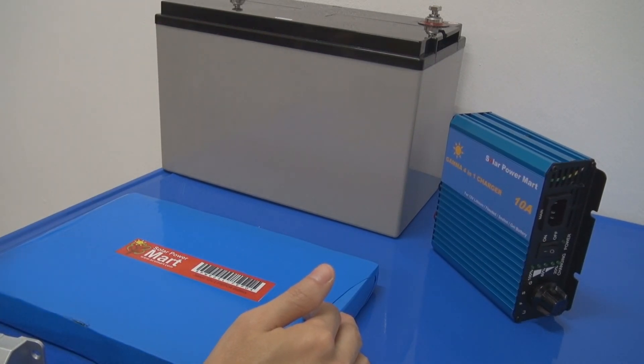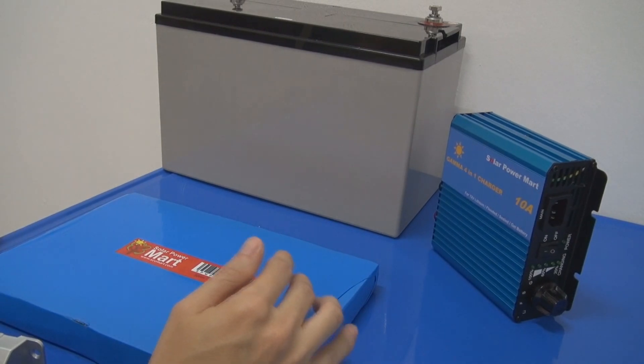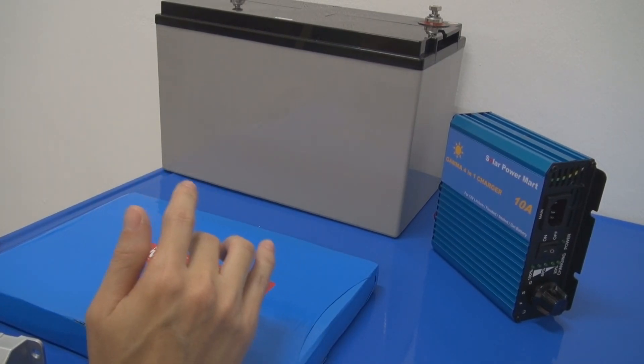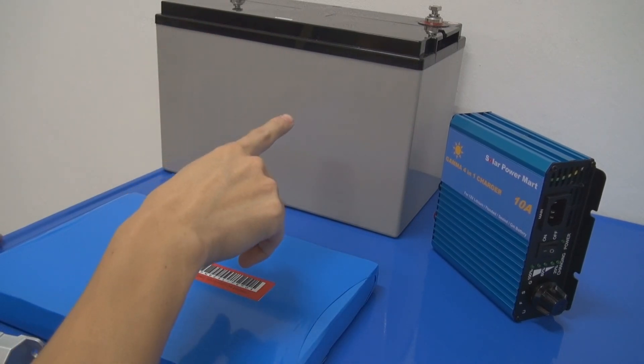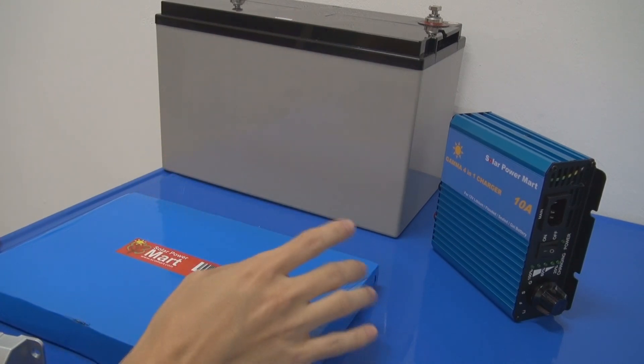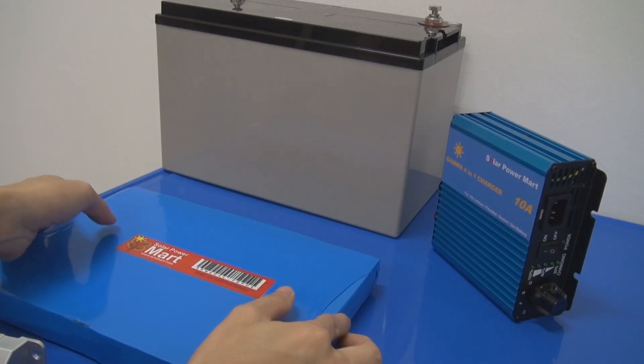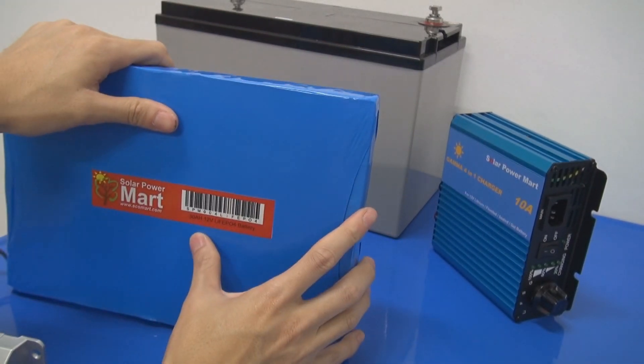Let's say you design your street light system. Every day you take about 20% DoD discharge because you want to prolong it and let it last about 2 years. Because you add in the temperature and things like that, if you cycle about 20% a day, it will last about 2 years plus with the temperature factored in. And let's say you upgrade to a lithium battery.